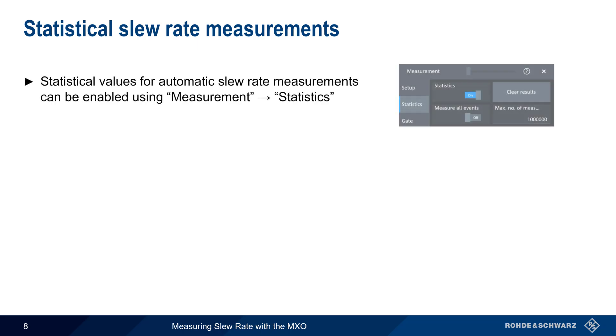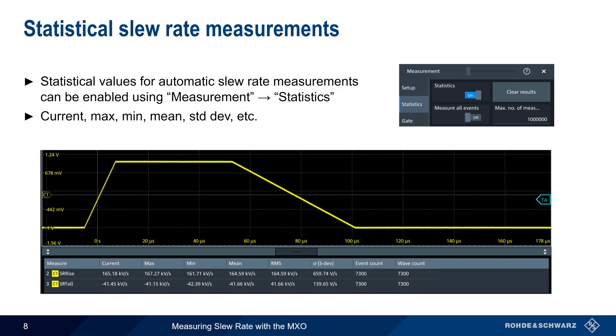Slew rate is often measured and reported as statistical values, and these can be enabled by choosing Statistics from the measurement screen. Statistical values of min, max, mean, standard deviation, etc. are all displayed at the bottom of the screen and are updated in real time. The Clear Results button can be used to clear and reset the statistical results.